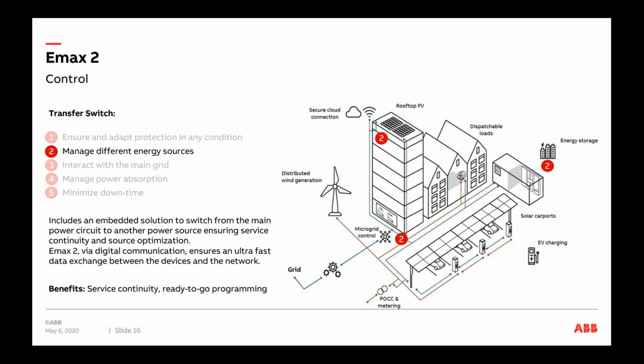quite common in most setups. We have ATS systems. When the main goes off, we have a generator supply. Sometimes in different setups, we have two transformers ready to supply onto the same power distribution system. So what we call automatic transfer switching is an embedded function in Emax 2. Now what that means is that Emax 2, without an external relay or without having to install separate logic and electrical interlocks through control relays in a quite cumbersome setup, can do it right within its electronics.